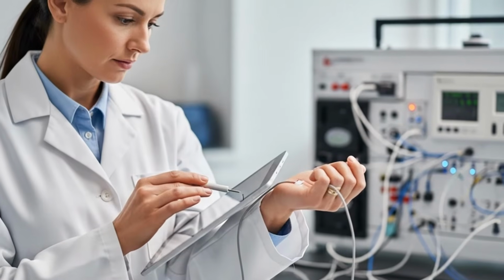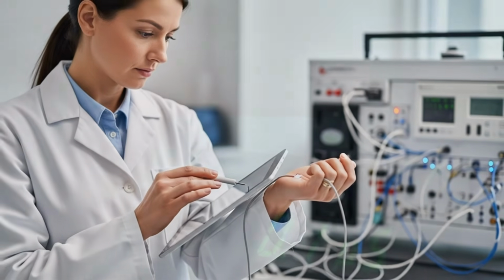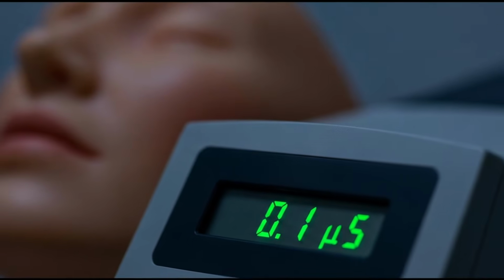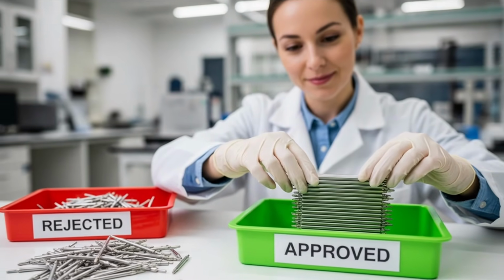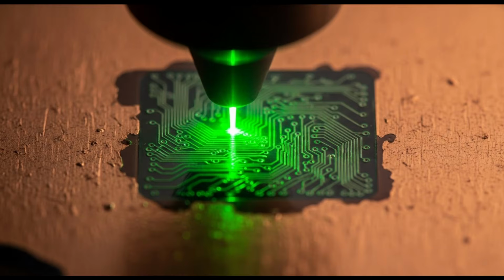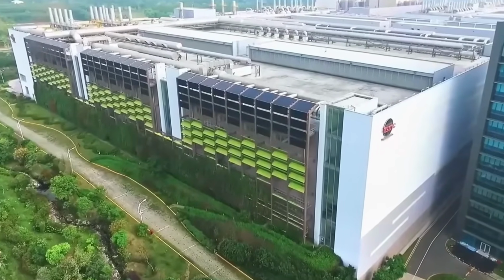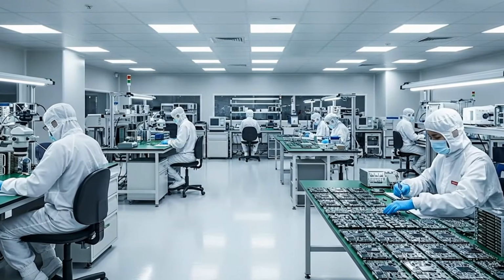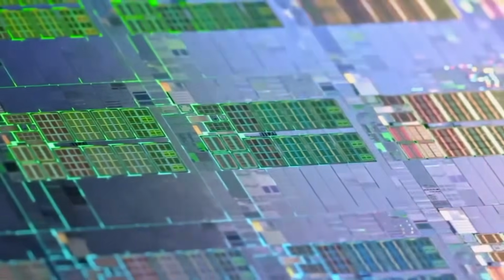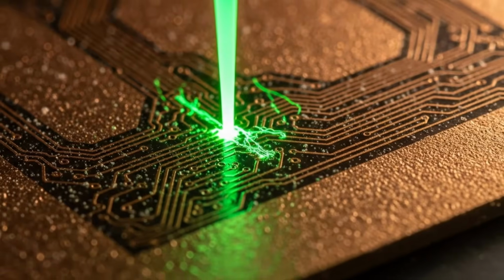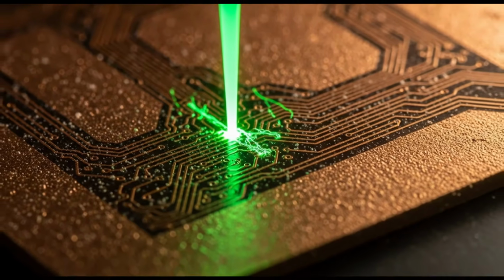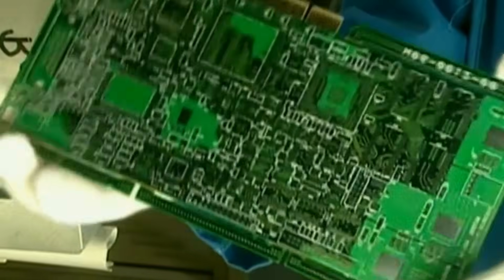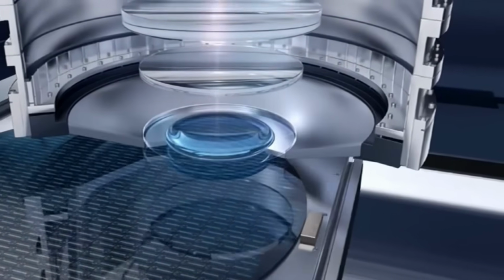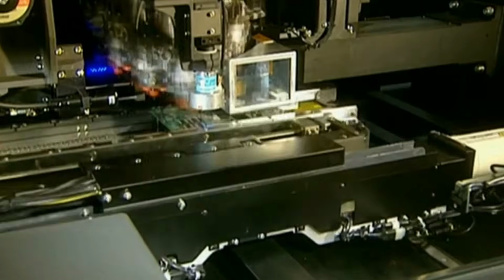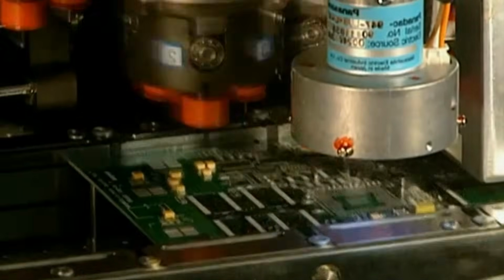Now we move to the core of the polygraph, the central unit. It is built in controlled environments similar to clean rooms used in the high-end electronics industry. The process begins with fiberglass sheets coated in copper, which are etched with photolithography to create circuits as fine as capillaries. These printed circuit boards serve as the physical foundation of all the electronics. At robotic stations, microprocessors, high-tolerance resistors, and signal amplifiers are soldered in place. The precision of this work is so exact that no human operator could match its consistency. This eliminates defects such as cold solder joints that could compromise the reliability of the device.